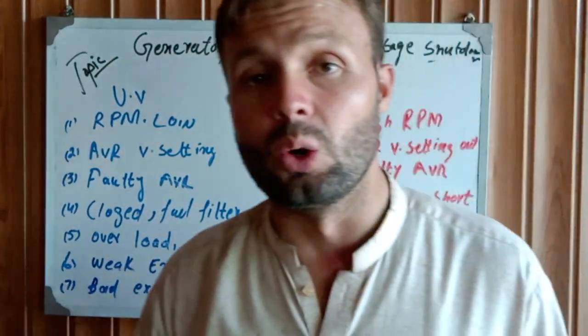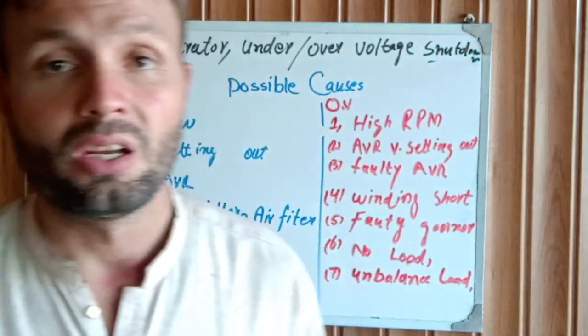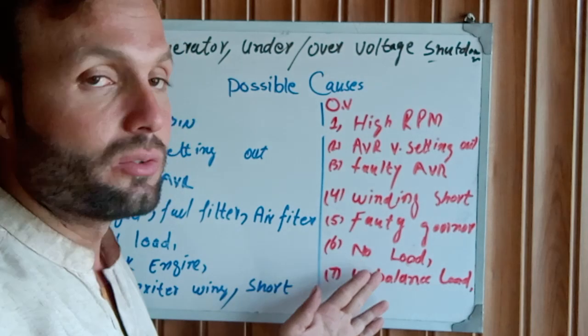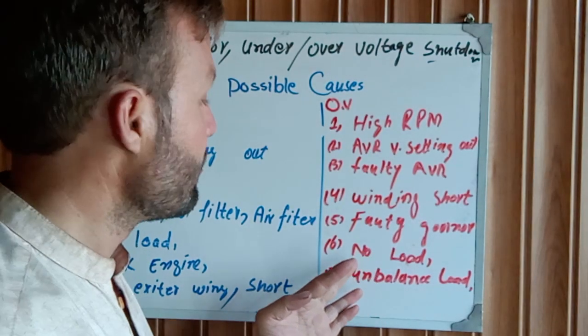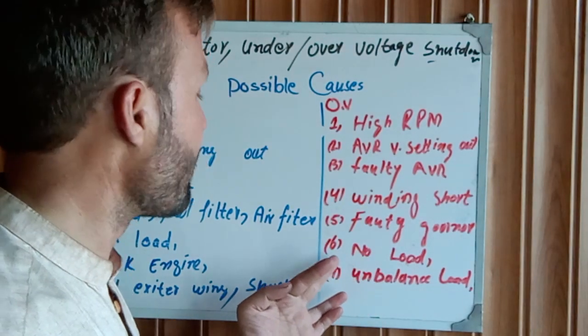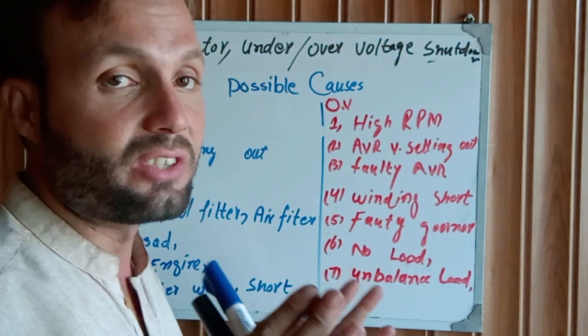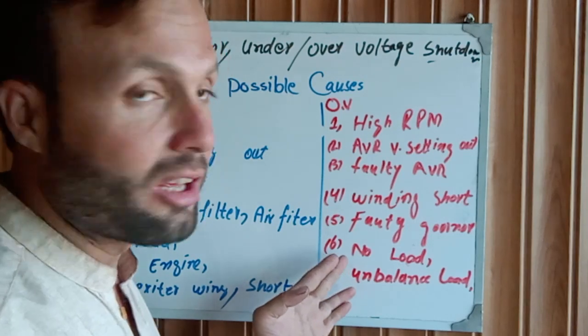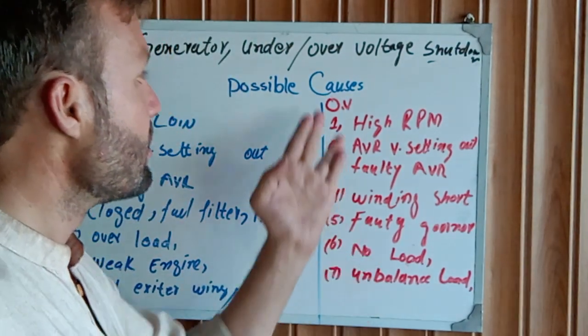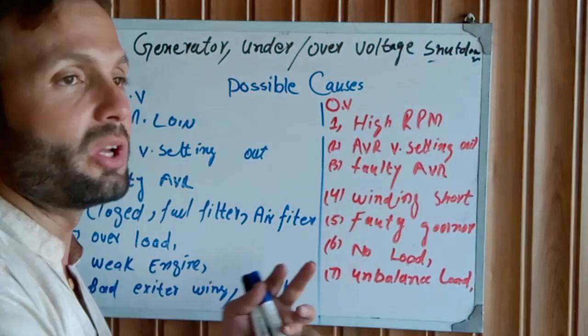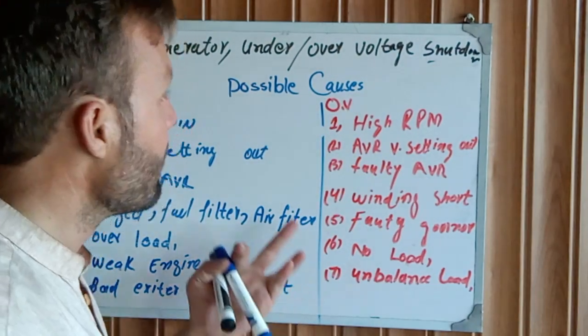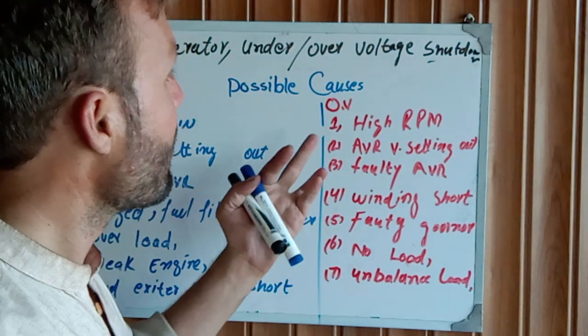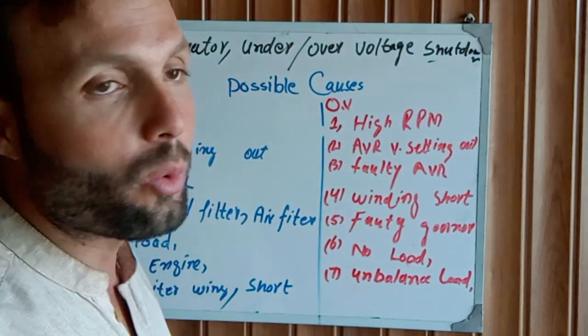Another cause is no load. If your engine is running without any load, the engine RPM can be slightly high. For a 1500 RPM, 50 Hz generator, the no-load RPM may be around 1550 RPM. When the engine is running without load and the RPM is high, the voltage is also high, which means the generator is in an over voltage condition and will trip.